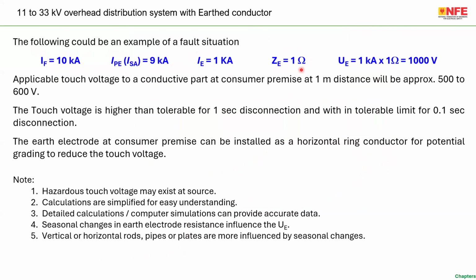Imagine the impedance of the earth electrode is 1 ohm. Please note that this is an arbitrary value. Just for explanation, I am taking 1 ohm. Don't think that 1 ohm earth electrode resistance is required anywhere. No, that is not a requirement. Now, under this condition, the total voltage gradient or EPR is something about 1000 volt. 1000 volt is the EPR.